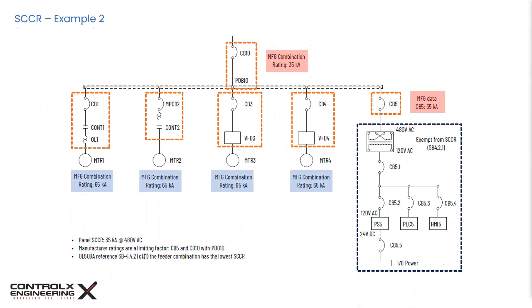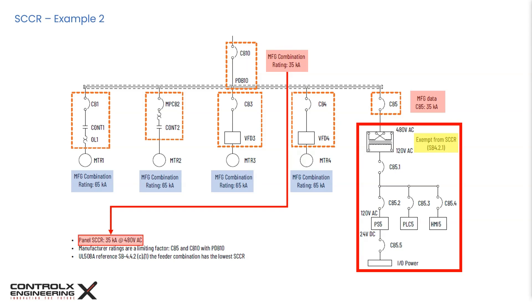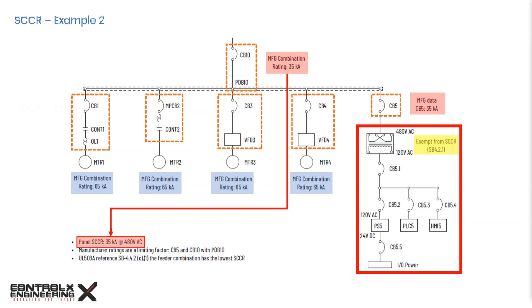In the second example, the main breaker CB10 and power distribution block PDB10 have a combined manufacturer rating of 35 kA, and CB5 also has a rating of 35 kA, while all sub-circuit components have SCCR values of 65 kA. The low-voltage circuit is again exempt from SCCR. The overall SCCR is limited by the manufacturer's combined rating for CB5 and CB10 with PDB10, so this panel's SCCR is 35 kA at 480V.